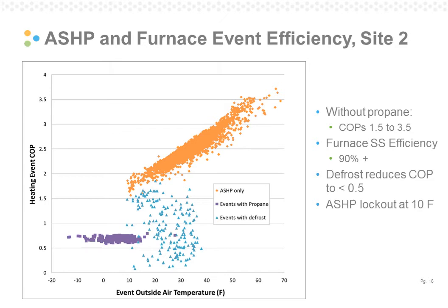The orange events on this slide are events where only the air source heat pump was running to meet the heat load. So COPs range from 1.5 to 2 at 10 degrees Fahrenheit and 3 to 3.5 when the outdoor air temperature is in the mid-50s. The purple events are heating events that only had propane to meet the heat load. And so for these events, the air source heat pump was locked out, so the air source heat pump wasn't running in defrost. So you can see that most of these events are occurring below 10 degrees. Again, that's because the air source heat pump was programmed to be locked out at 10 degrees.